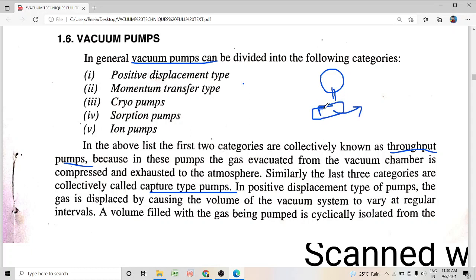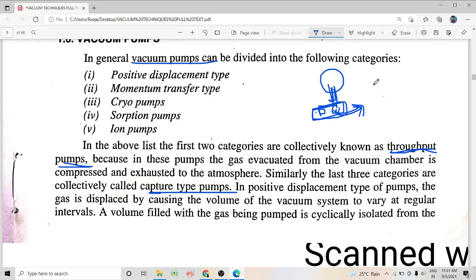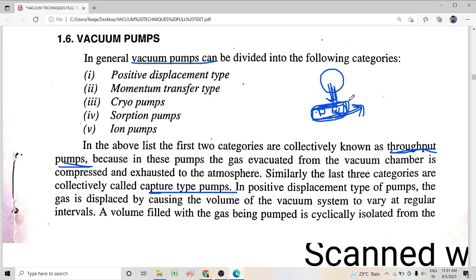In a throughput pump, the gas taken from the vacuum chamber is compressed and then given out to the outside atmosphere by the pump. Whereas in capture type pumps, the gas taken from the vacuum chamber is trapped on the inner walls of the pump itself by means of processes like adsorption, condensation, etc. The gas molecules extracted from the vacuum vessel are trapped on the inner walls of the pump itself — it is not given out to the outer atmosphere.